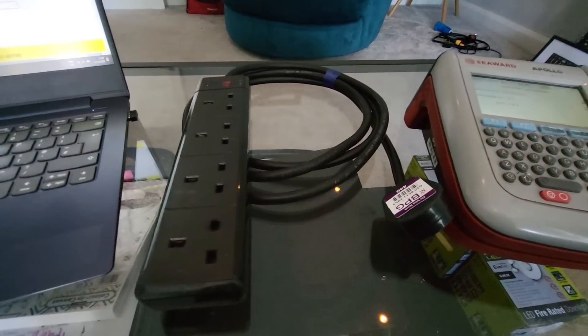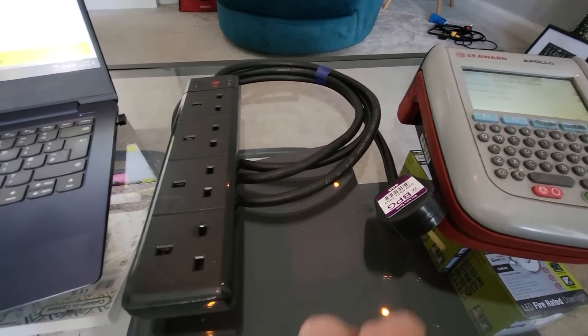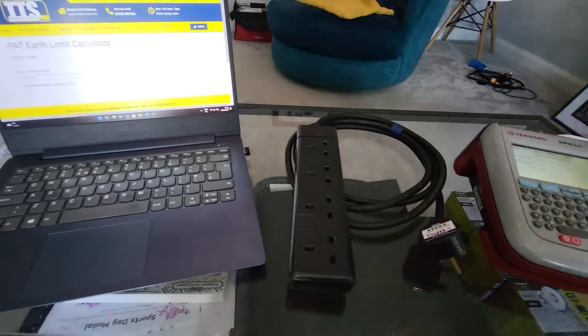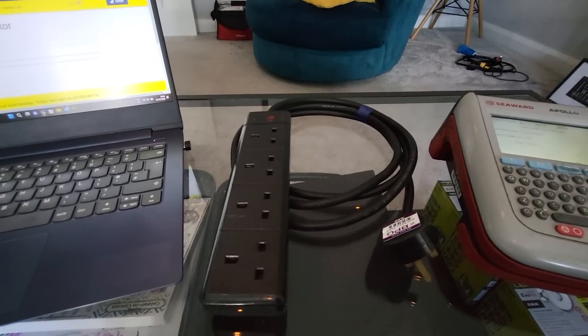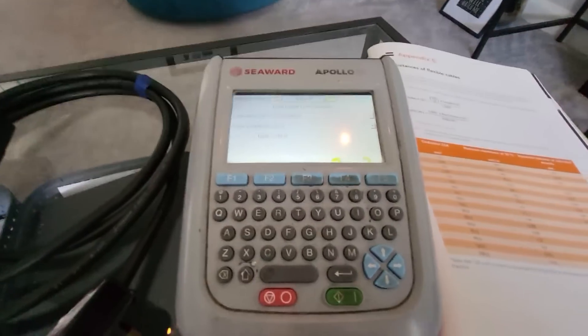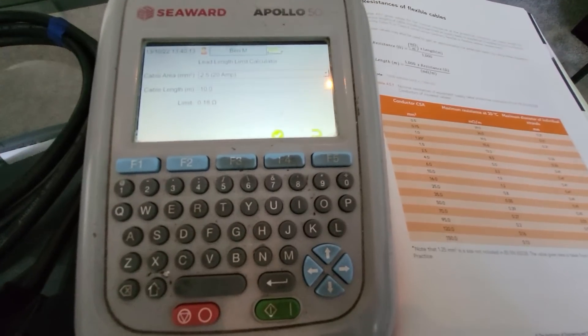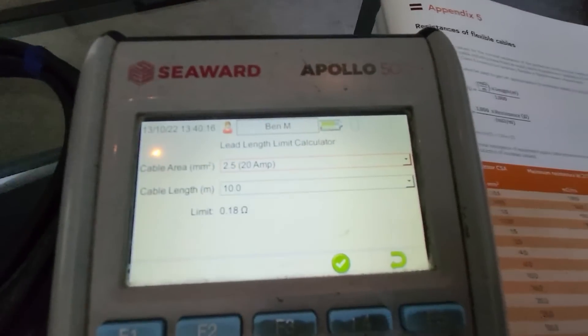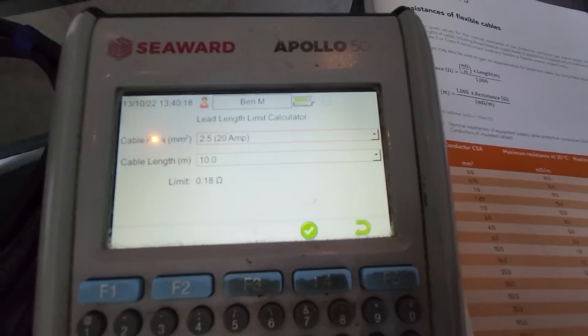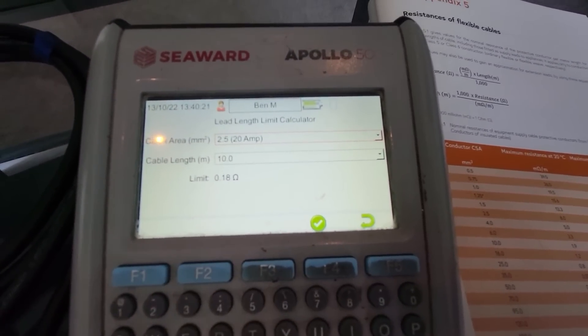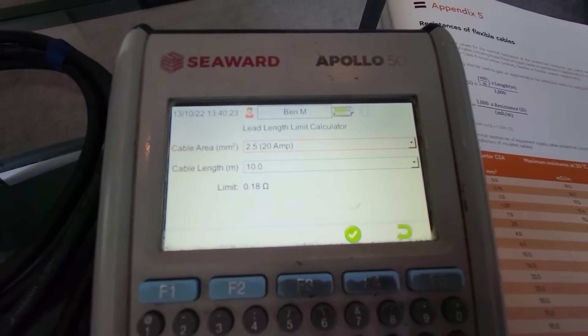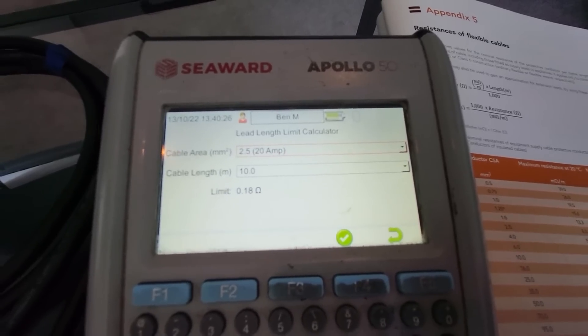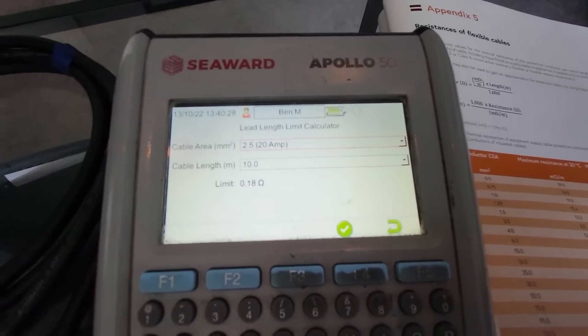Basically, you just have to, because of the nature of those entry-level machines, you just have to do a quick calculation and work it out. If you're lucky enough to have a downloadable machine like I do here with the Apollo 500, there is actually a built-in lead length limit calculator. So as you can see there, I've just popped in 2.5 millimetre cable area, 10 metre length, and it gives you the same reading of 0.18.